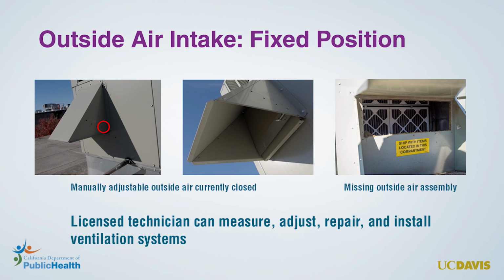While this should be done periodically, it's important to do an extra inspection if there's a concern they were closed during a wildfire event. As previously discussed, a common ventilation system type is the fixed outdoor air system. These intakes, positioned on the suction side of the fan, serve to draw in fresh outdoor air.